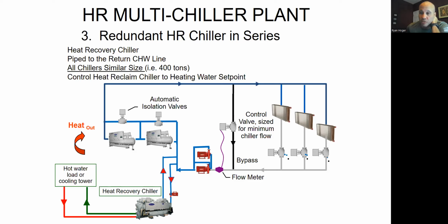But yeah, if you have a building that needs cooling in the winter, let's say it's a hospital, you do need cooling in the winter, right? Even in Scandinavia, you probably need cooling in the hospital in the winter, operating rooms and stuff like that. But then out in front, you have the drop off for the emergency room, and you want to snow melt that because you don't want people slipping when they go into the emergency room. And then maybe you got a helipad and you want to snow melt the helipad. You could take the heat from your building when you're running your heat reclaim chiller, and send the waste heat to the snow melt and to the helipad and melt the snow on those. You could definitely do that. That would be cool.